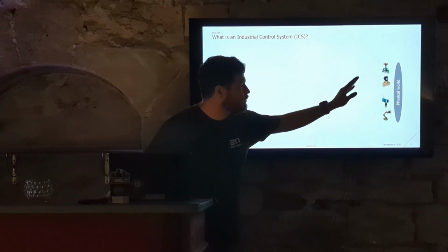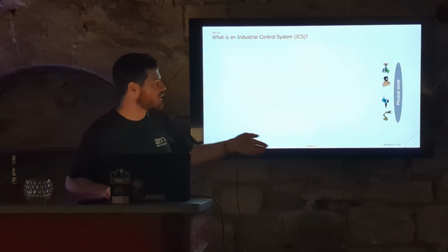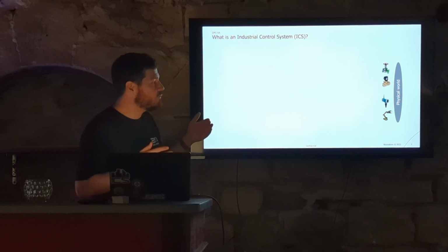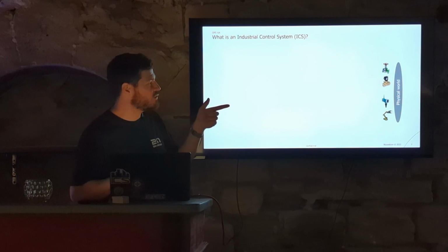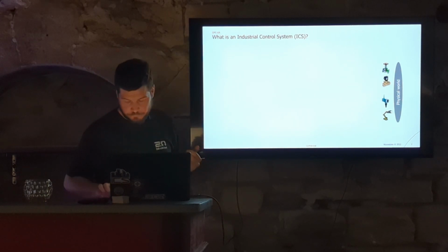The actuator will do the opposite. It receives an electrical signal and it will transform that into a movement. For example, here you have an electrovalve. The idea is that if it receives 0 volt, it will allow the flow through the pipe. And if it receives 24 volts, it will close the valve and then the flow will stop.